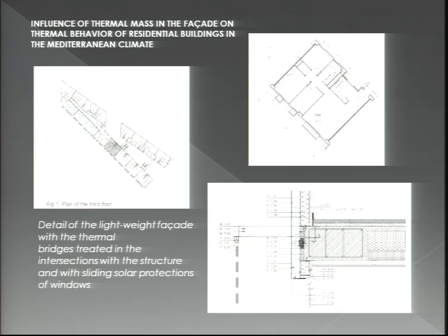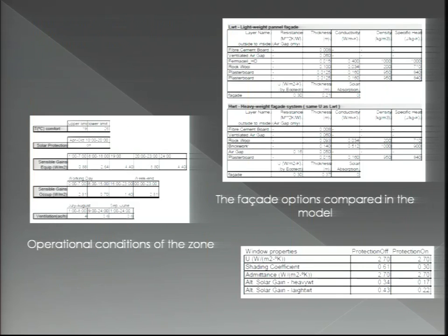This figure shows what Ecotect can do for existing buildings. In one study, researchers took a residential apartment unit, selected just its facade, analyzed all the layers inside, and compared lightweight versus heavyweight construction. This comparison affects cost, material selection, and thermal comfort. When doing such a study in Ecotect, you need to input material properties including thickness, conductivity, density, and specific heat.